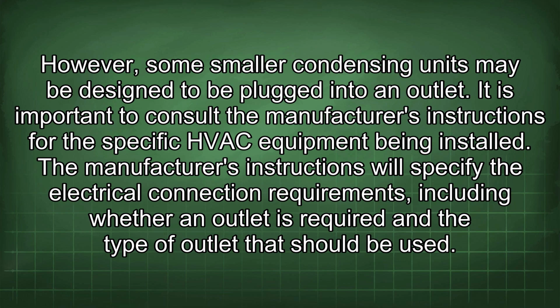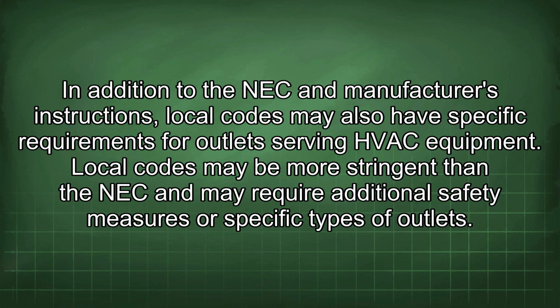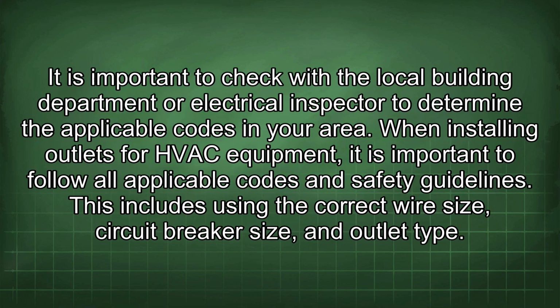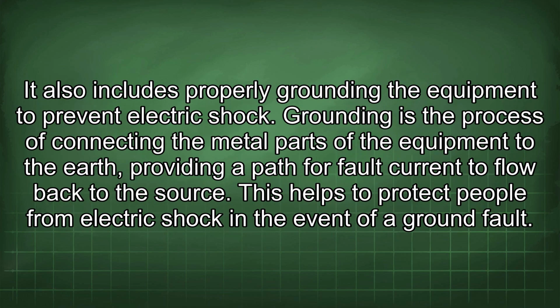In addition to the NEC and manufacturer's instructions, local codes may also have specific requirements for outlets serving HVAC equipment. Local codes may be more stringent than the NEC and may require additional safety measures or specific types of outlets. It is important to check with the local building department or electrical inspector to determine the applicable codes in your area. When installing outlets for HVAC equipment, it is important to follow all applicable codes and safety guidelines. This includes using the correct wire size, circuit breaker size, and outlet type. It also includes properly grounding the equipment to prevent electric shock.